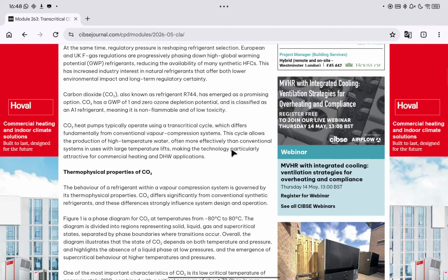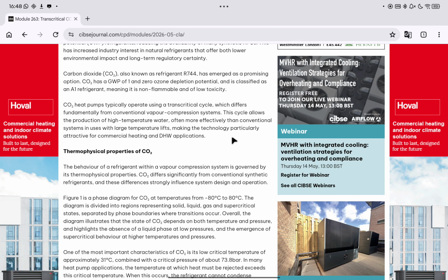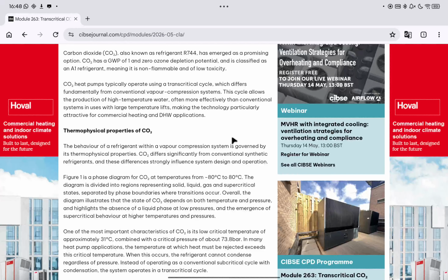Thermophysical properties of CO₂. The behavior of a refrigerant within a vapor compression system is governed by its thermophysical properties. CO₂ differs significantly from conventional synthetic refrigerants, and these differences strongly influence system design and operation. Figure 1 is a phase diagram for CO₂ at temperatures from -80 degrees C to 80 degrees C. The diagram is divided into regions representing solid, liquid, gas, and supercritical states, separated by phase boundaries where transitions occur.